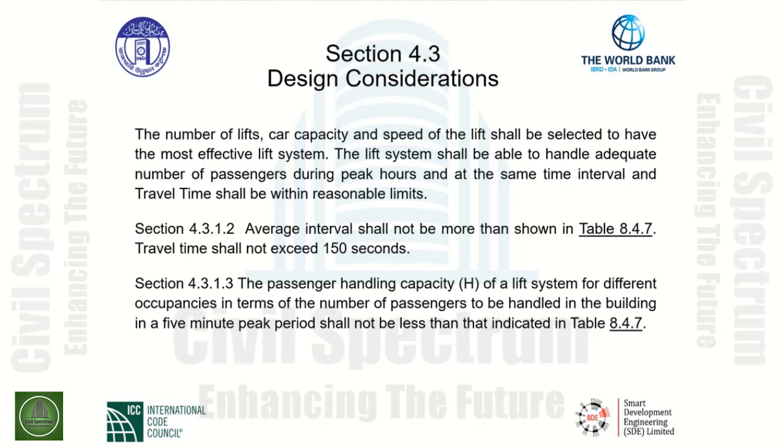Section 4.3.1.2 indicates that average interval shall not be more than shown in Table 8.4.7. Travel time shall not exceed 150 seconds. In this section, it begins to lay out a reference in the form of Table 8.4.7 that we will look at, and a maximum travel time not to exceed 150 seconds.